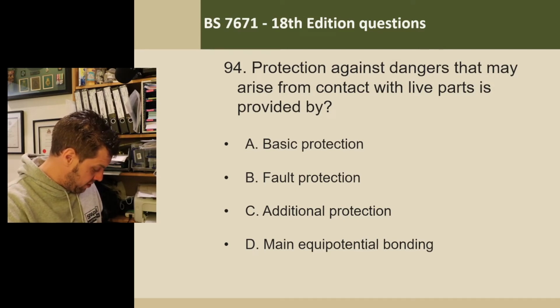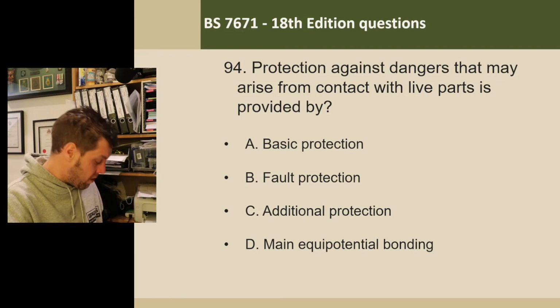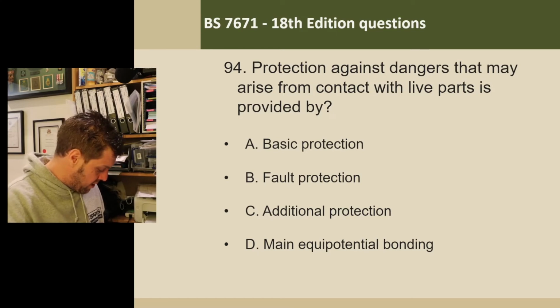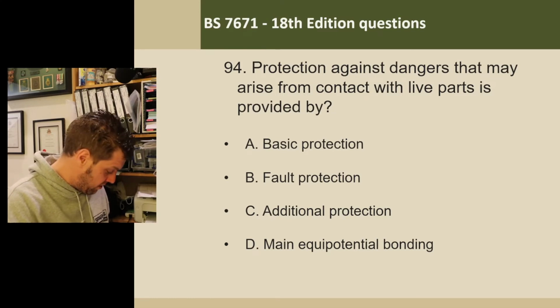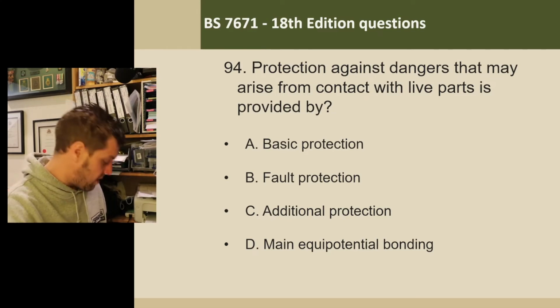Basic protection - it used to be called direct contact. I've got a note in my regs book here: persons and livestock shall be protected against dangers that may arise from contact with live parts of insulation. This protection can be achieved by one of the following methods: preventing the current from passing through the body, or limiting the current. That's basic protection. That's the answer.